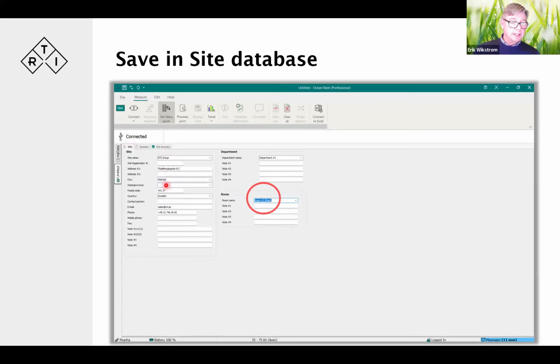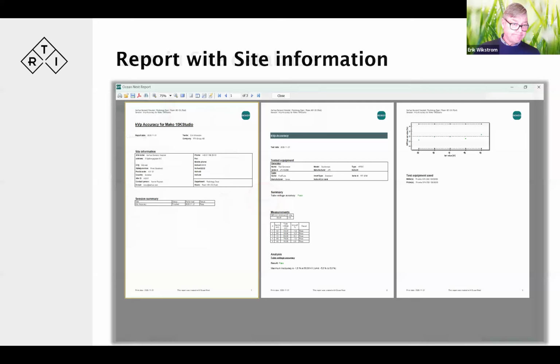So we have site, we have address, we have the contact email. This only has one department, so that's populated immediately, but there's a choice here of which room inside this department we're located in. So we need to pick a room, and the room has also associated with it a generator and a tube. Once we have all that, the report is populated with all that information. Here we have site information, we have the tested equipment with serial numbers, etc., and all the rest. So we actually have a documentation of where we were, what individual modality we were working on, what the result was, and what equipment we used. So we have documented everything.